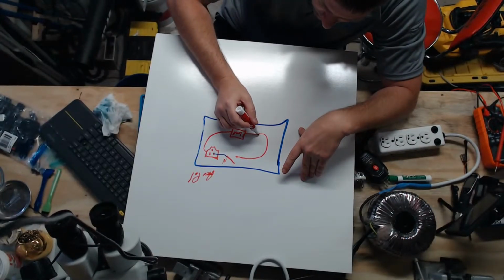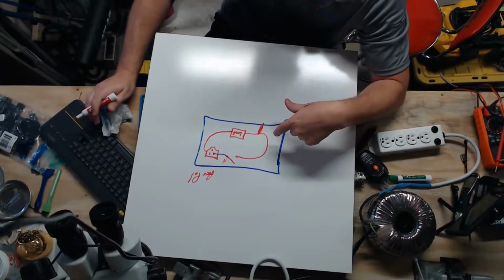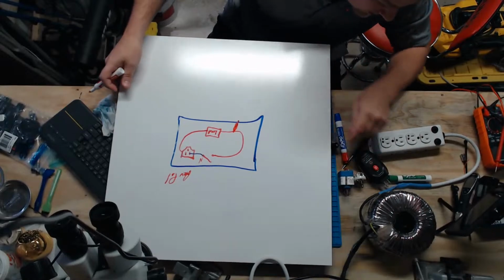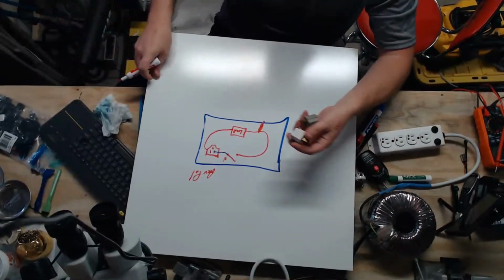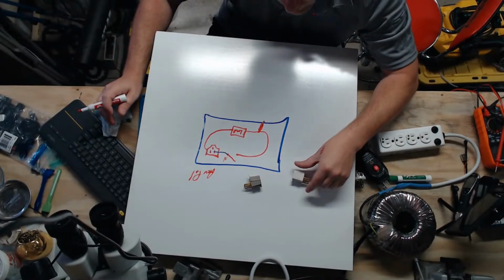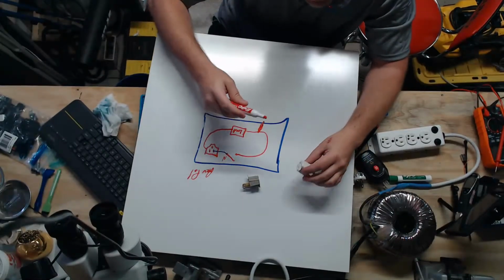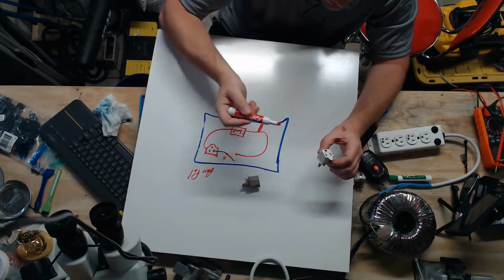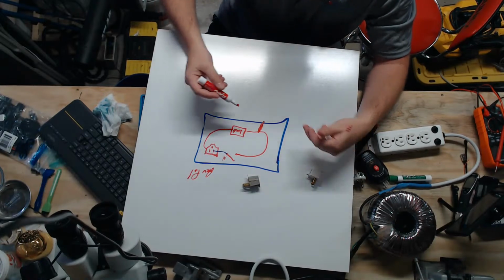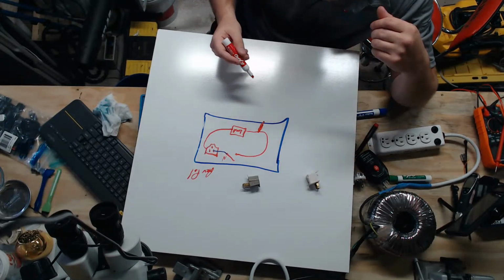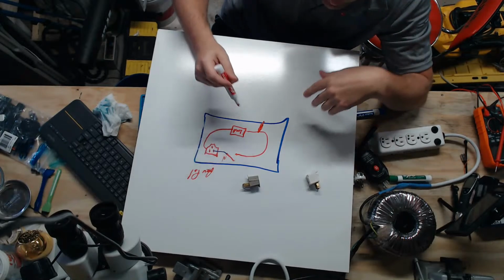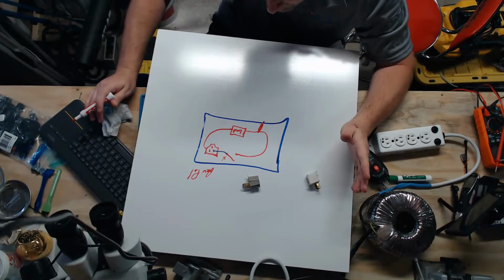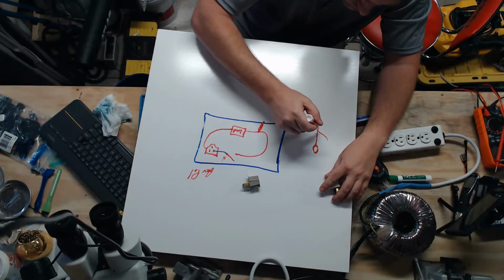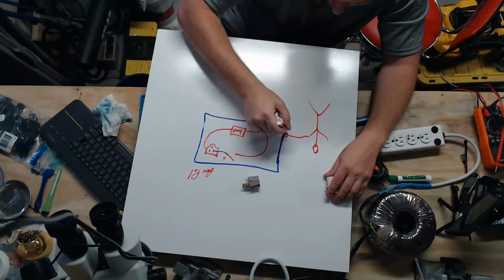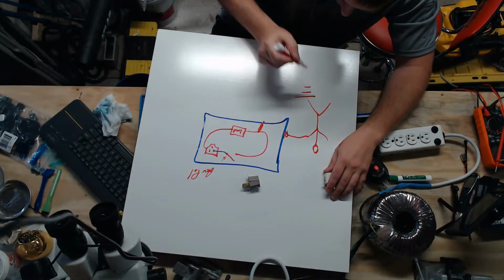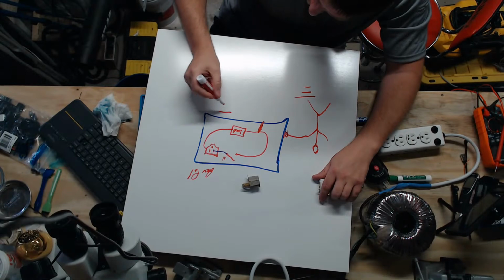So let's say you have an electrical short where there's a wire inside the device and it shorts itself to the chassis. Okay, and this is going to go right into these guys. All right, so these guys right here, the whole purpose to these things being a pain in the butt is because you are taking away your ground, and you can see right there. So if you have an electrical short inside your device and you get rid of your ground, you're counting on neutral carrying away all that crazy current, which it can't do. All right. So you, the person, is here. You touch the ground, you are at ground potential. The chassis is supposed to be at ground potential.